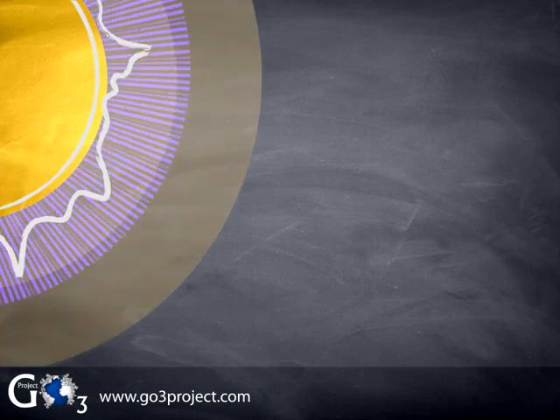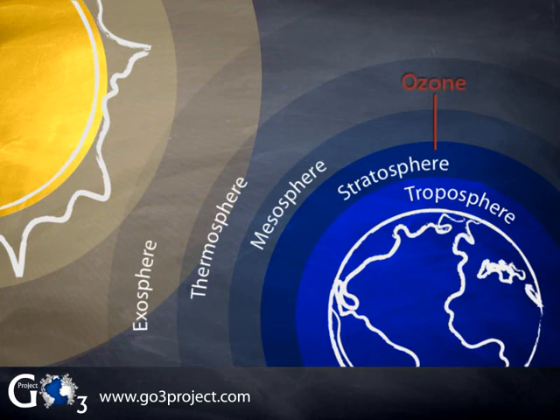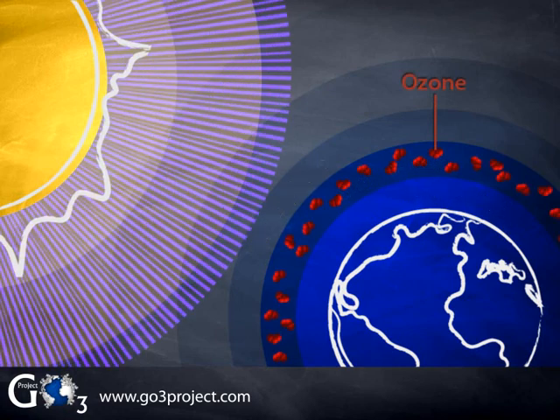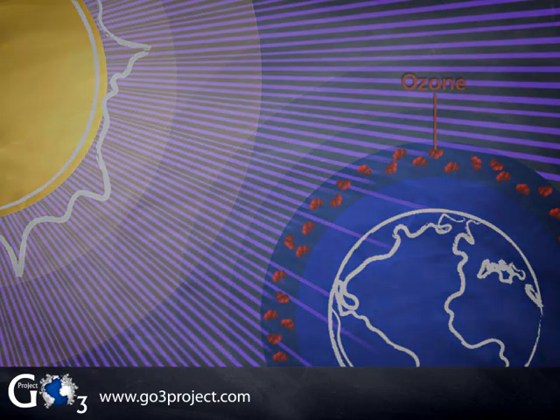The most widely used method for measuring ozone is based on absorbance of ultraviolet or UV light. As you may know, ozone in the stratosphere absorbs ultraviolet light to protect the earth from harmful ultraviolet rays coming from the sun. This same property of ozone, the absorbance or blocking of UV light, may be used to measure ozone concentration in the air we breathe. Here we will show how an ozone monitor based on UV absorbance works.